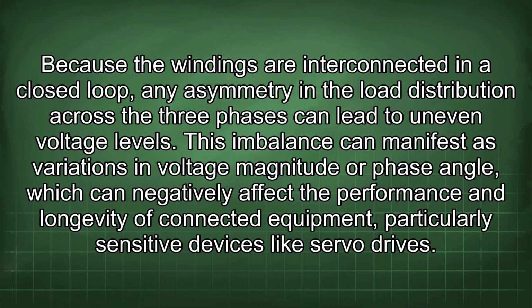Because the windings are interconnected in a closed loop, any asymmetry in the load distribution across the three phases can lead to uneven voltage levels. This imbalance can manifest as variations in voltage magnitude or phase angle, which can negatively affect the performance and longevity of connected equipment, particularly sensitive devices like servo drives.